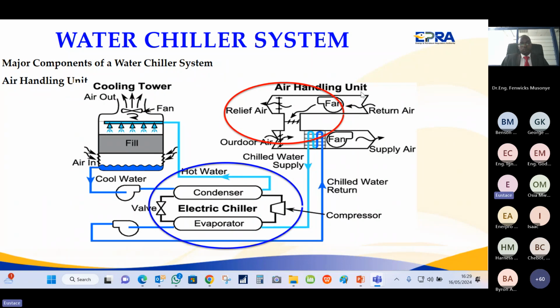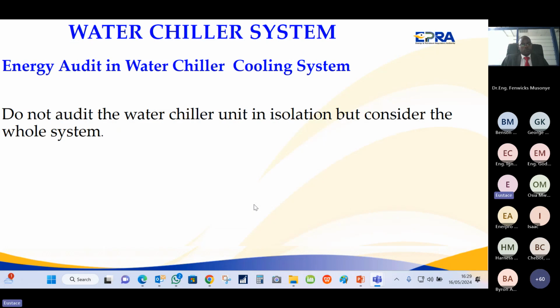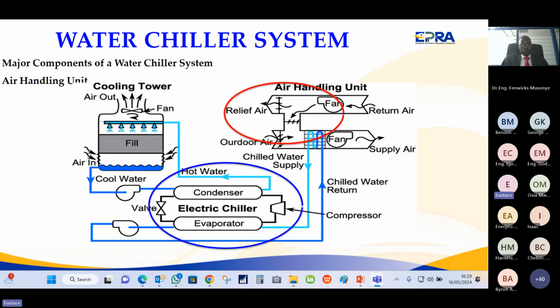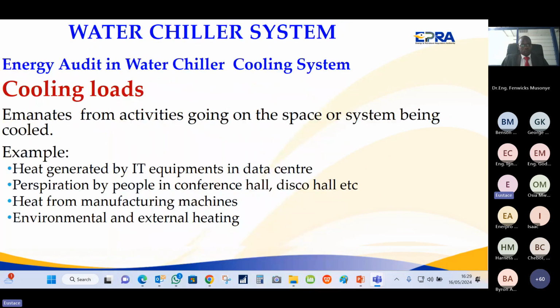You also need to understand whatever you are dealing with. If it's a theater, you don't limit the amount of air. If it's a room with people inside, you don't reduce the air going in. So those measures are also good. You can introduce VFDs and also a control system to ensure that not all compressors run together, because such a system might have several compressors that can be switched off and run one at a time. Any question?